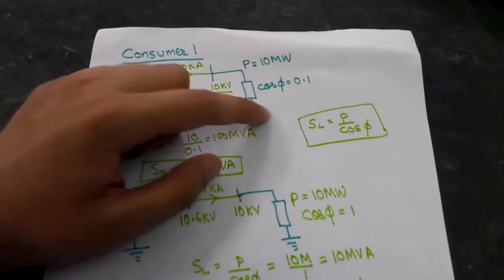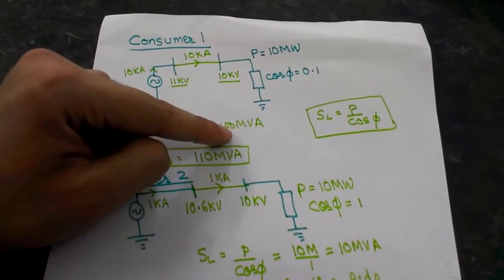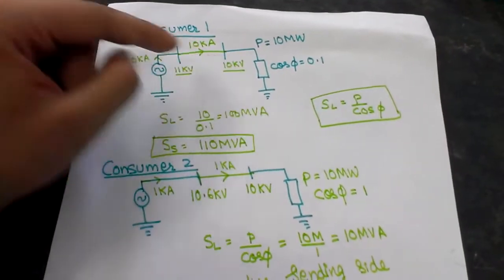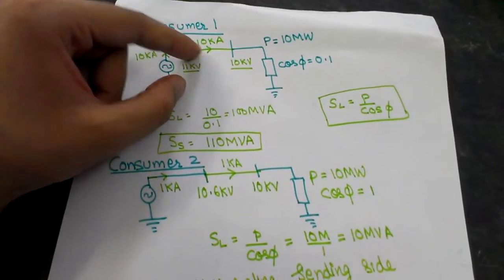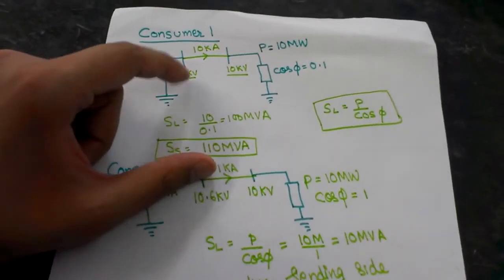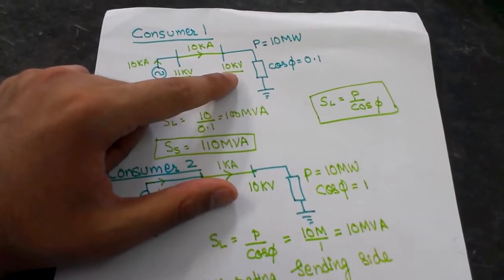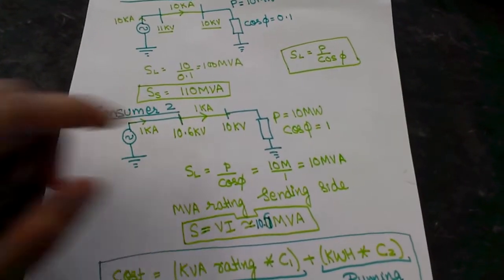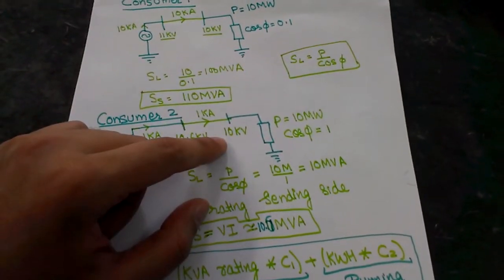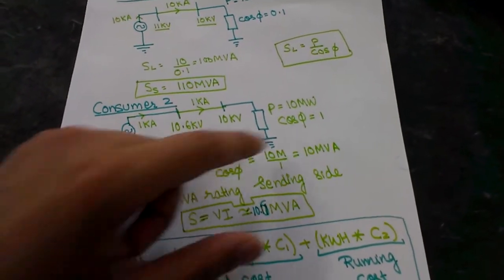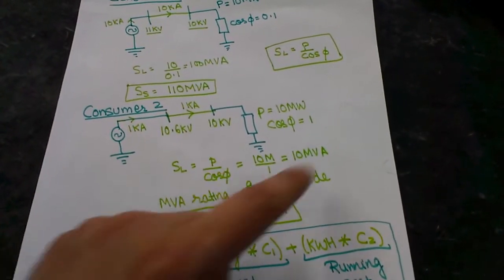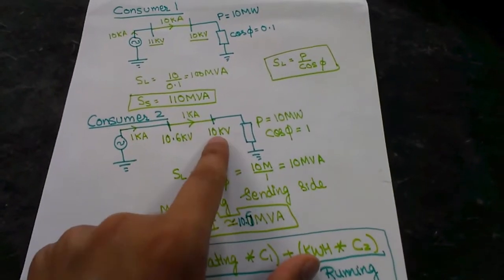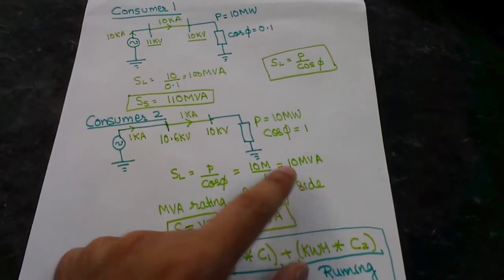So this consumer draws 100 MVA. Dividing by 10 kilovolts gives 10 kiloamps — the power utility must supply 10 kiloamps to this consumer. Let's say there was a voltage drop of 1 kilovolt, so the utility generates 11 kilovolts at the sending end and the customer receives 10 kilovolts. For the second consumer, also consuming 10 megawatts but at cos φ = 1, the apparent power S = P / cos φ = 10 MVA. Dividing 10 MVA by 10 kilovolts gives only 1 kiloamp of current.